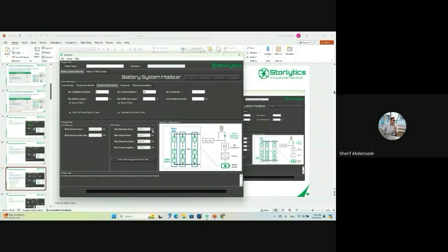And this gives you the 100th percentile of the usage profile. So it tells you the maximum discharge power in your usage profile was 1.1 megawatt. The maximum charge power was also 1.1. And for maximum energy for both discharge and charge, it gives you those values as well. But again, these are maximum values, so the 100th percentile. Yesterday, we went over the histograms, and we understand that you could probably get away with a much smaller capacity, since these maximum quantities are not used very often.